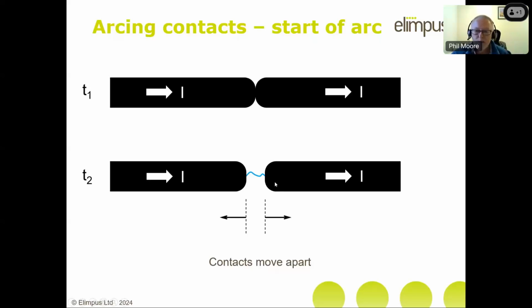Usually in a circuit breaker, one of them is fixed, and only one of them moves, but the effect is the same. And that's a very good state of play for a circuit breaker, because you know exactly where the arc is. The reason you know where the arc is, is that when you move these contacts apart, you don't get an arc at the outset. When you start to move them apart, you melt the contact material and draw out a very thin thread of molten material, which then develops into an arc. So you can actually guarantee that this arc is going to be across these contacts.